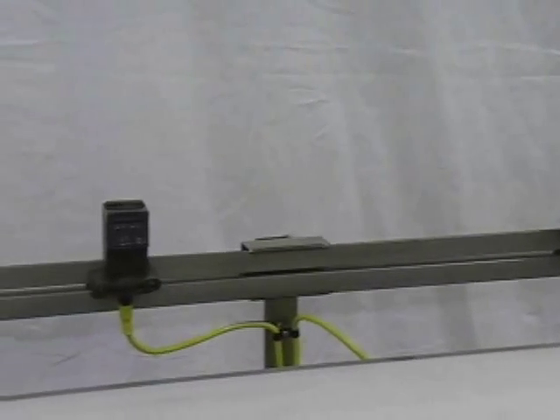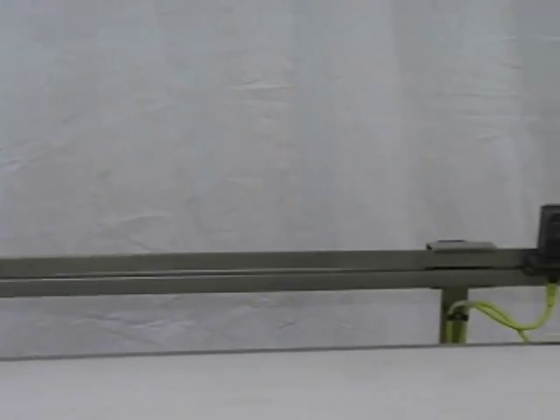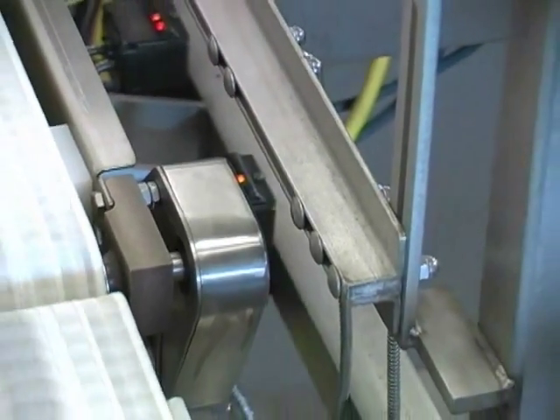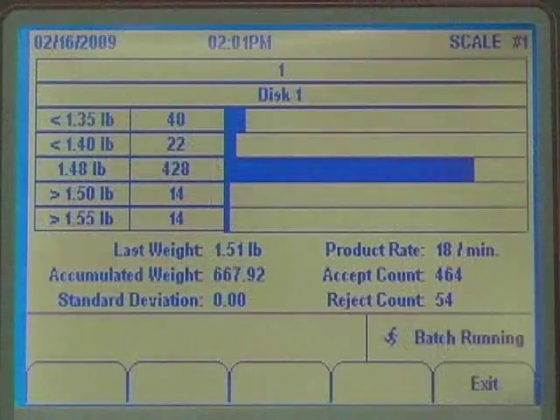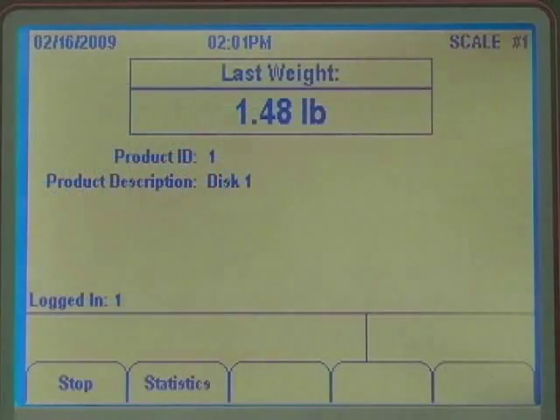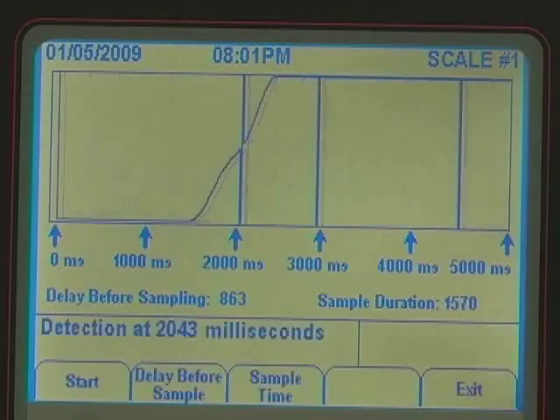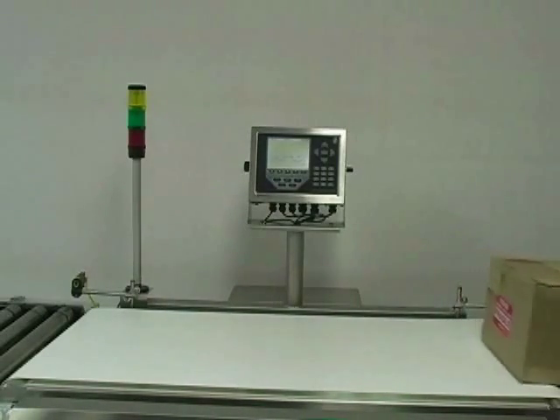Sensor position is key to achieving consistent and accurate weighments. MotoWay systems provide a full-length adjustable sensor positioning system that reduces initial setup time and also makes changes to the weighing system very easy when new products or containers are sent across the scale system for the first time. The MotoWay integrator features an easy-to-read screen showing product weigh values, item count in five different ranges, and diagnostic information. Calibrating the system for use with new products is an easy process. A unique distribution curve graphic illustrates how a package enters and exits the scale, ensuring accurate, repeatable weighments of a wide variety of packages.